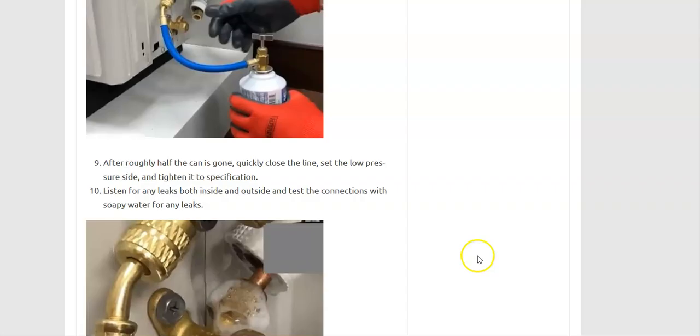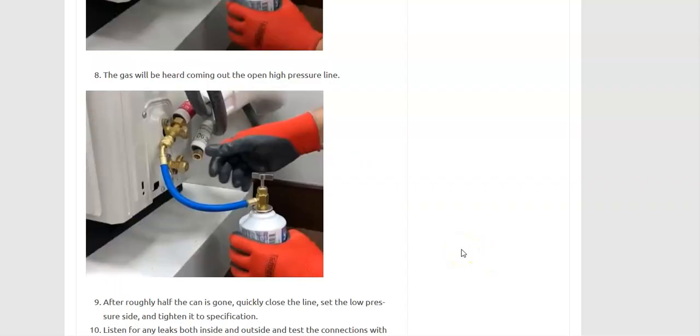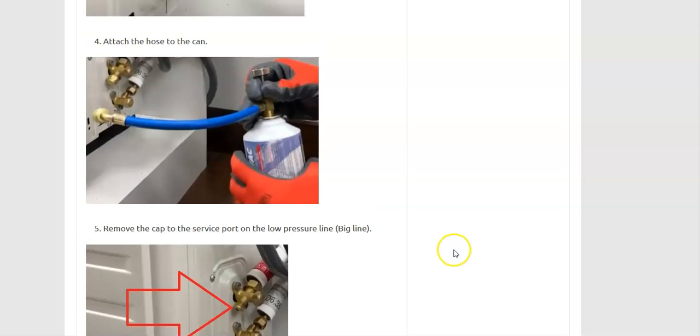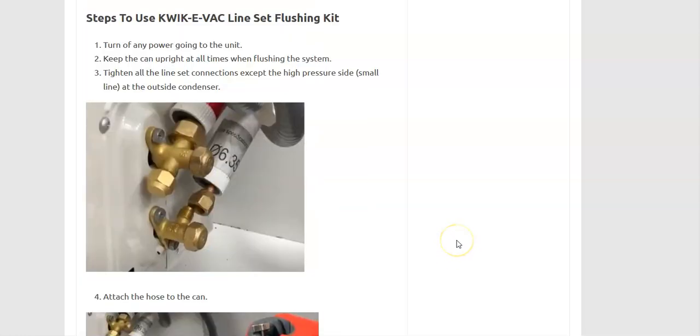This is supposed to blow out all the air and any small particles. You let it blow out for a short while, like five to ten seconds or whatever the instructions say. Then you bolt on that last connection on the high pressure side. Since the can is still open and pushing into it, it also pressurizes everything, so you can test for any leaks with soap and water. That's the basics of this Kwik-E-Vac line set flushing kit.